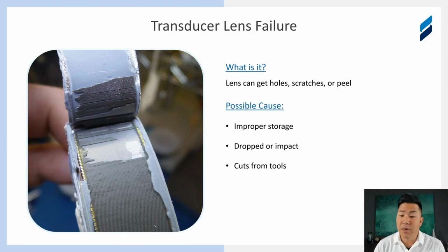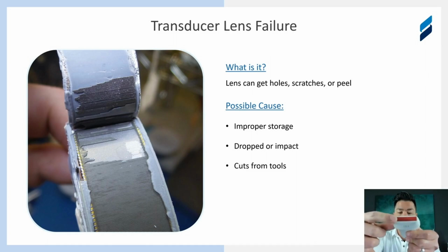This is an example of a lens failure on a transducer. As you can see, this is pretty severe. Again, I have a transducer here to show you, and on this particular probe, it's a red lens. But these are vulnerable to holes, scratches, peeling back, cuts, whatever have you, to this really rubber lens that is in between the patient and the crystal that sends and receives that sound. And generally, this is caused by just use of the transducer and maybe some accidental damage.